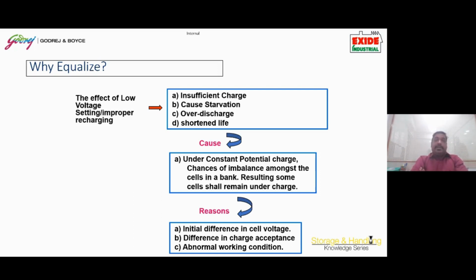So when you put such batteries on discharge, the cell with the lowest float voltage will discharge faster, reach the end cutoff, and go into a state of deep discharge faster than the other cells. When recharging, this cell which has gone into deep discharge will take much more time to get recharged than the other cells.